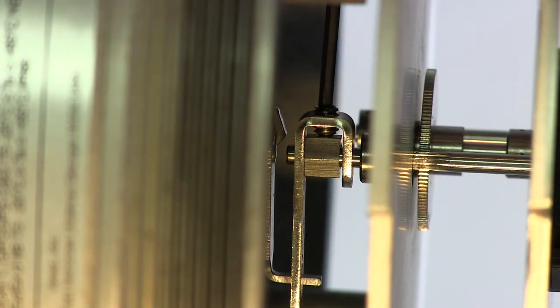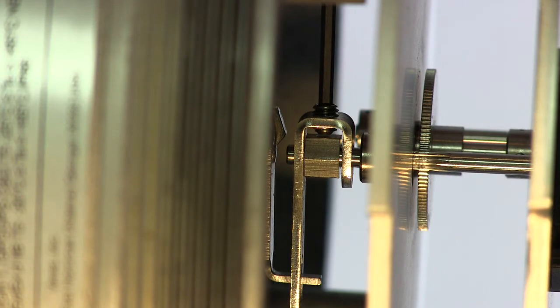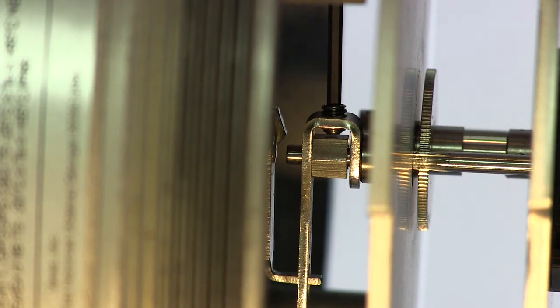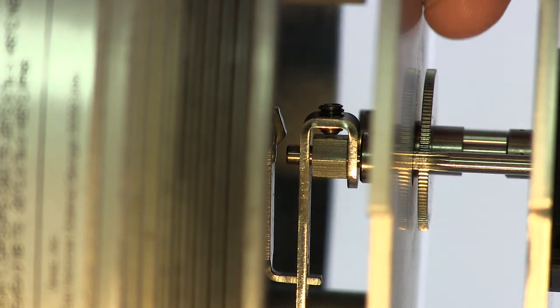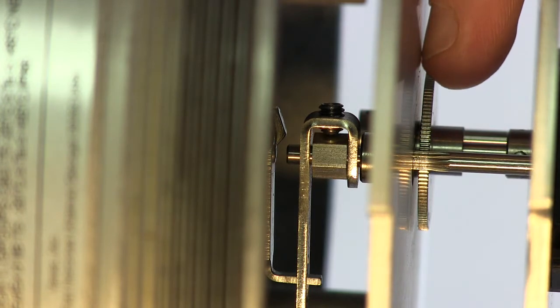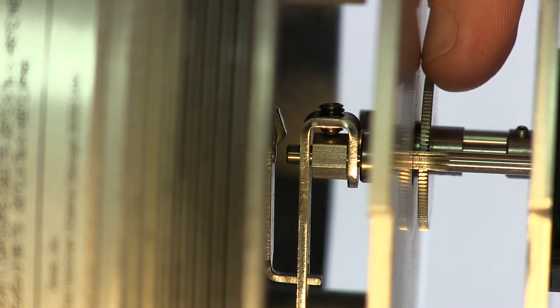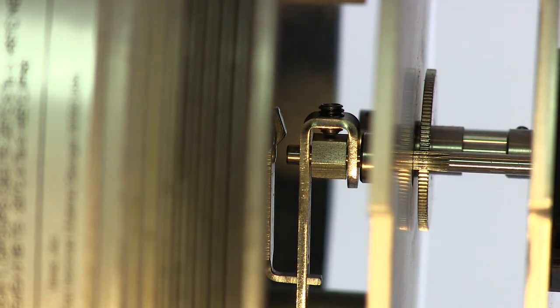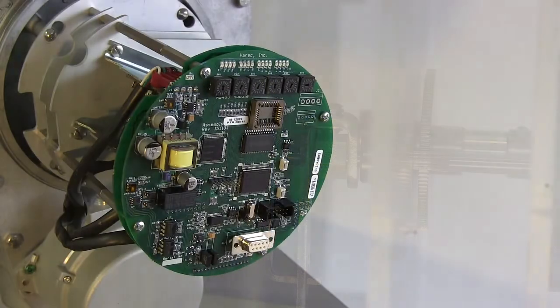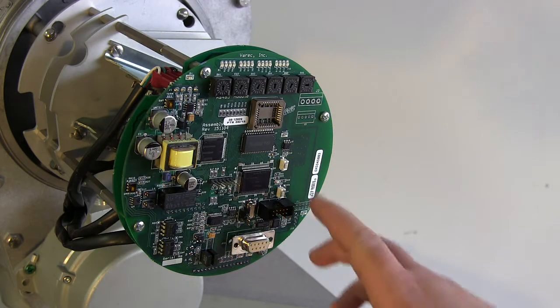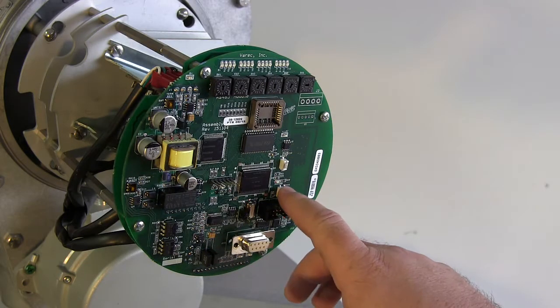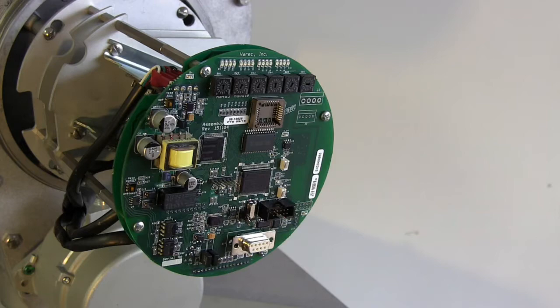To use the LED method, loosen the set screw on the encoder driveshaft slotted coupling just enough so that the encoder rotates freely without rotating the coupling. Be careful not to loosen it too much or the coupling will fall. Now activate the LEDs on the communication circuit board by pressing SW8. The LEDs will be enabled for about three minutes. The level indicated by the LEDs is the same whether you set the encoder to forward or reverse reading.